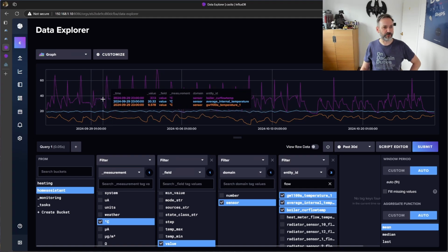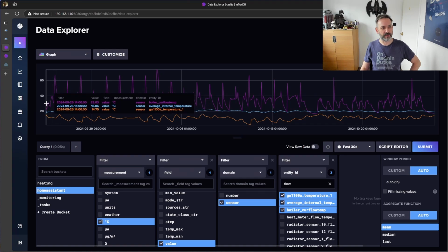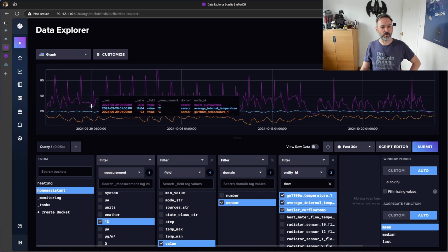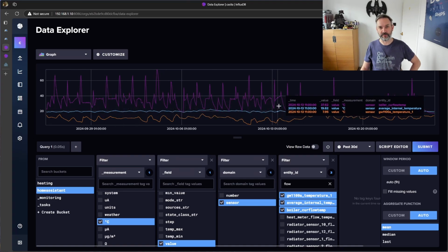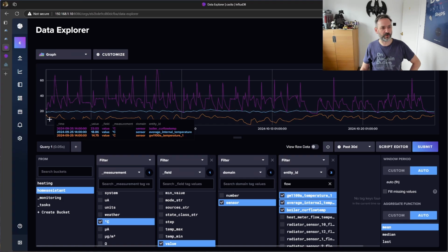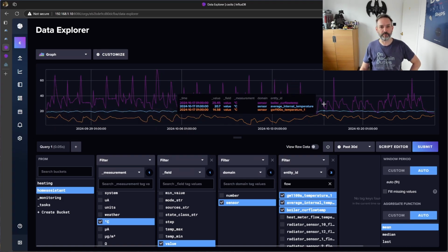But you can see some of these runs where it's ran pretty steadily, but pretty much we're hovering around this kind of median line here. And that's because I've set the boiler's flow temperature to 32. So it is going to go up and down as the boiler itself cycles. And I mentioned that earlier in the video, just due to the size of the boiler, it always overshoots the target, and then it'll drop, and then it'll overshoot the target again, and then it will drop. But it's hovering around that kind of set point. So with those kind of temperatures, it's had no problem keeping the house nice and warm.